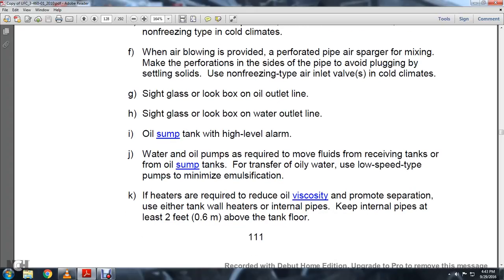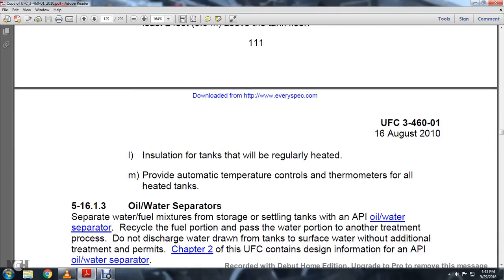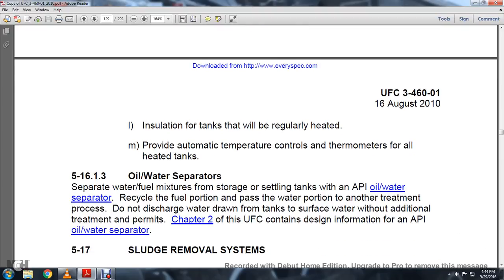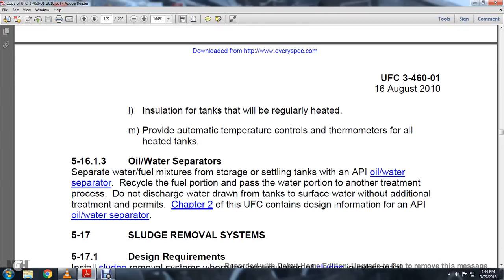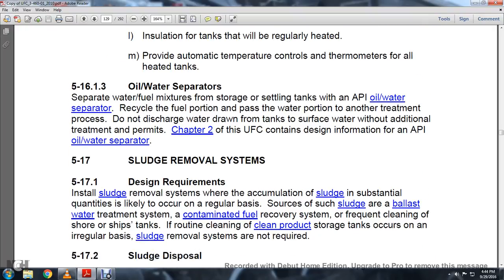If a heater is required to reduce the viscosity to promote the separation, either for the tank wall heater, keep the internal pipes at least 2 feet above the tank floor. Insulate tanks that will be regularly heated, and provide automatic temperature control and thermometers for the heated tanks. 516.1.3 Oil water separators with separate water fuel mixture storage and settling in the API oil water separator, recycle the fuel portion. The water portion goes to another treatment process; do not discharge water from the tank surface water without additional treatment permits. Chapter 2 of the UFC contains the design information of the API oil water separator.